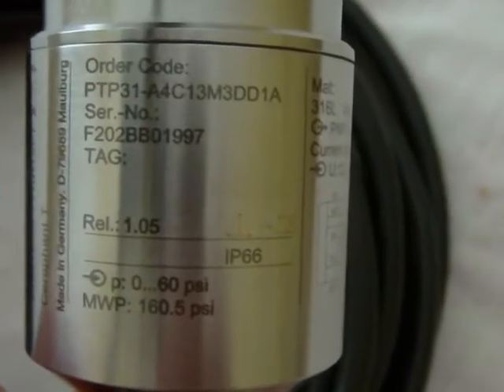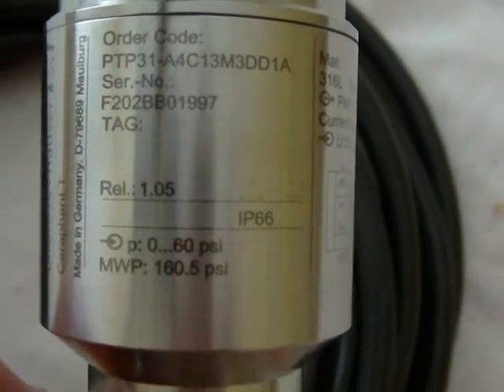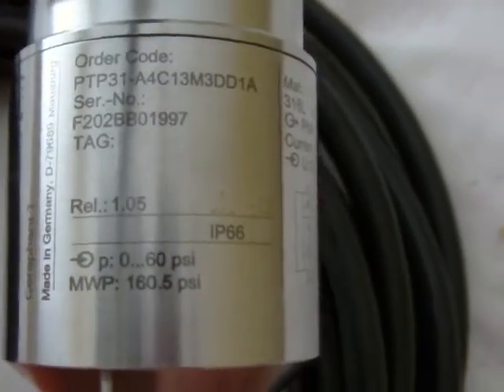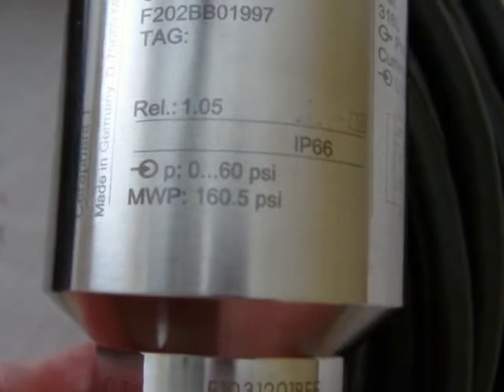I don't know if you can see if it says gauge. It's 4 to 20 milliamps. Current consumption: 60 milliamps. I'm trying to find the part where it says this is a 60 PSI part — there it is. It's a zero to 60 PSI. And maximum pressure, which won't damage it, is 160.5.